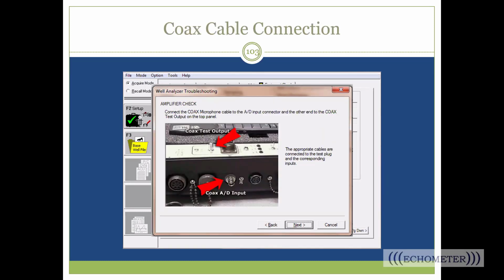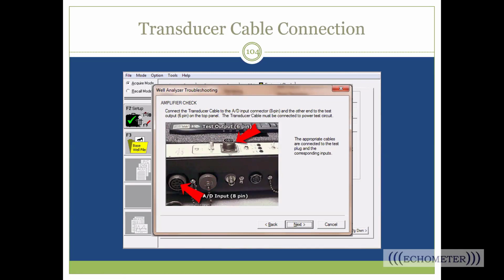So the first check is going to be your microphone cable. You'll plug one end of the microphone cable into the top of the well analyzer and the other end to the side where you would normally plug it in when you acquire data, and click next. Now we're going to plug in the solenoid cable, your transducer cable. You plug that 6-pin connector that you would normally have plugged into your pressure transducer, or if you've got a coil cable that you would normally have piggybacked onto that, and you've got your load cell or your PRT, that's what you're plugging in: that 6-pin connector that would plug into one of your sensors that goes on the top of the box.